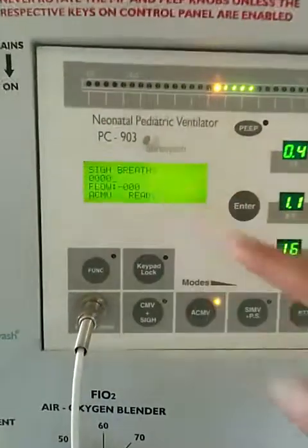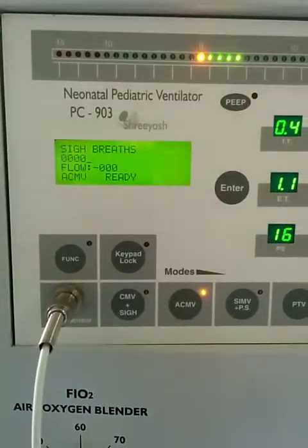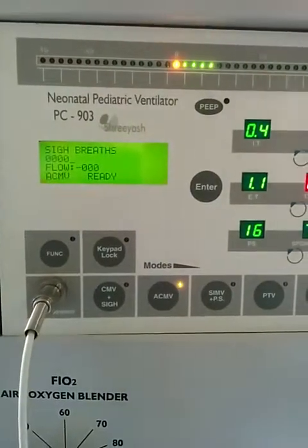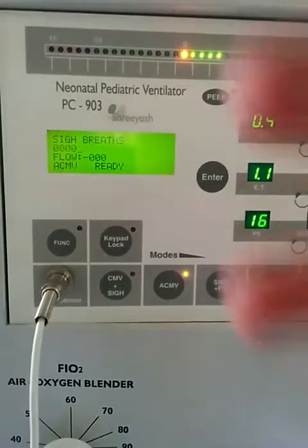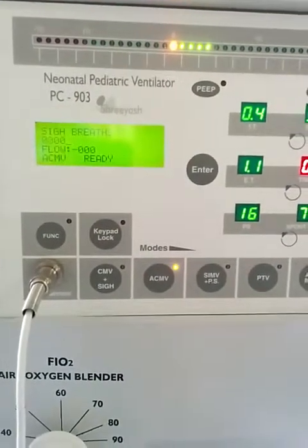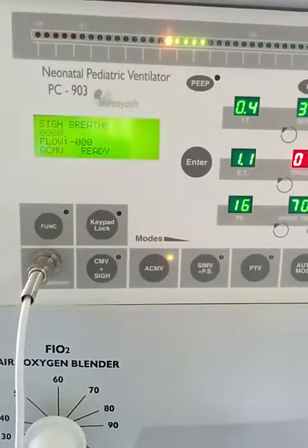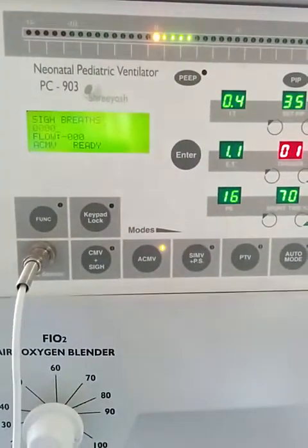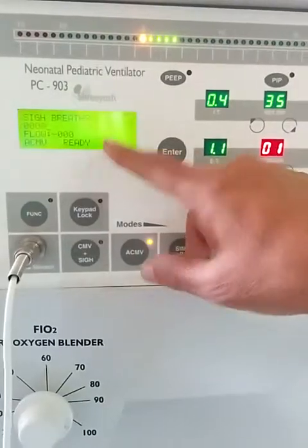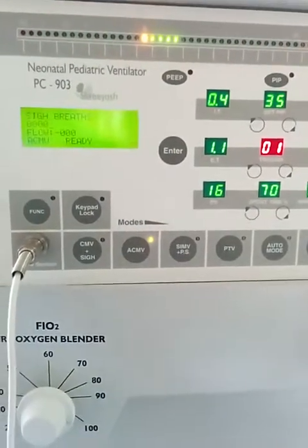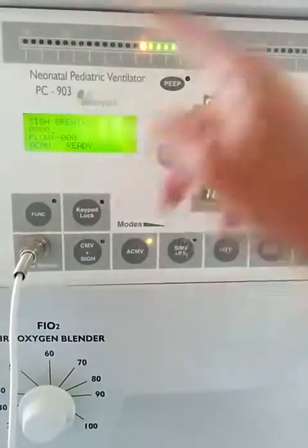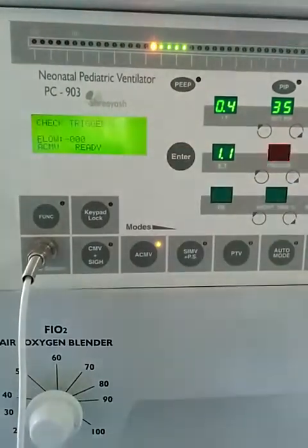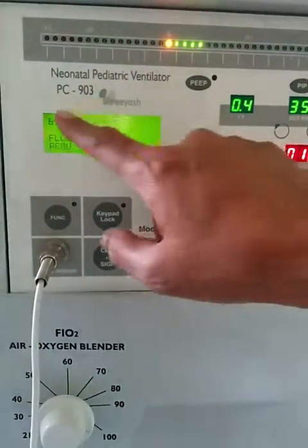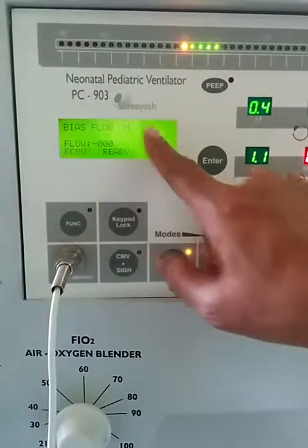Now it sets the sigh breath. A sigh breath is one breath that gives 1.5 times more air, pushing more air into the patient's lung to open up the deeper and the smaller alveoli. If you set the sigh breath, it will deliver one big breath after every 100 breaths. So I again don't set it. I just press enter, and now the display will show you the bias flow is on. Assist control mode is ready.